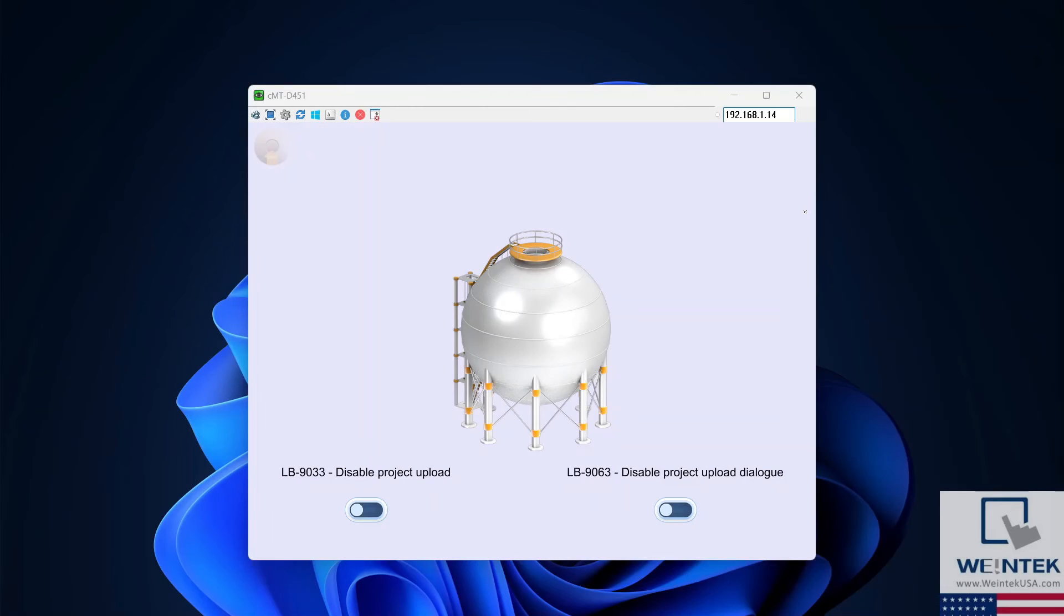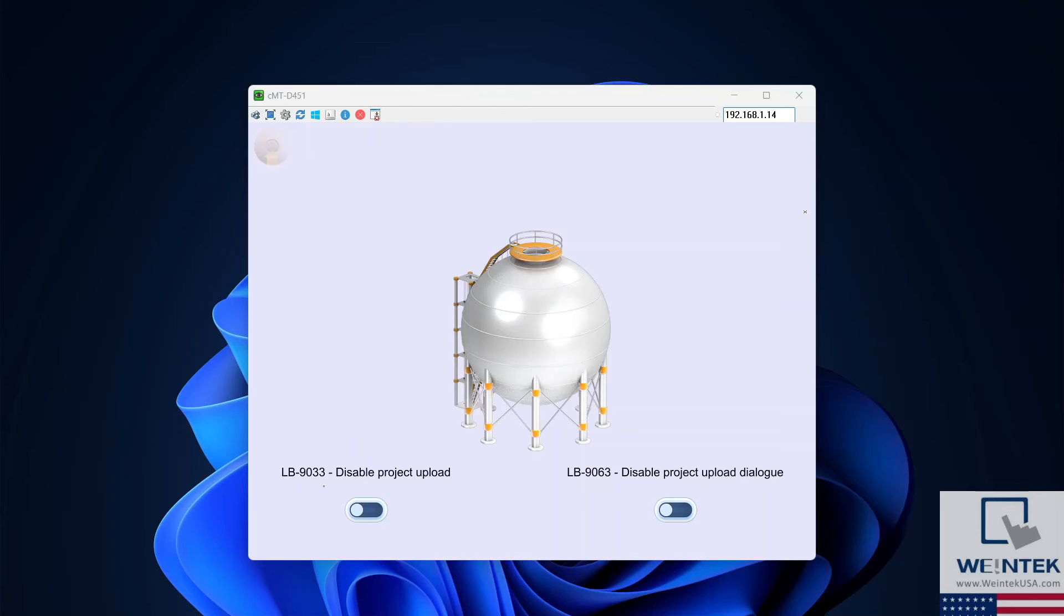We have a couple of system tags used to prohibit project upload from an HMI. LB9033 disables HMI upload function completely, and LB9063 disables the upload dialog when the USB flash drive is inserted.